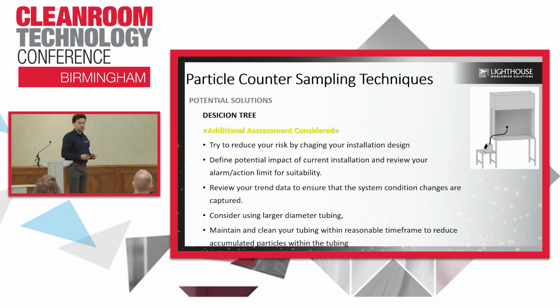And maintain and clean your tubing within a reasonable time frame to reduce accumulated particles. To clean your tubing, never use pressurized gas. Never use an ultrasonic bath because you are damaging your tubing. The best thing is to fill it with 70% IPA, put it into a U shape, and move it a little bit up and down, and let it dry. In this way, you will be able to clean it faster and easier. So maintenance should be in place. For the pharma industry, this should be part of the contamination control strategy.